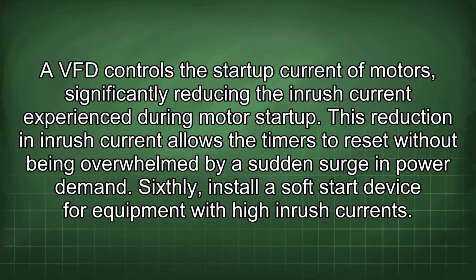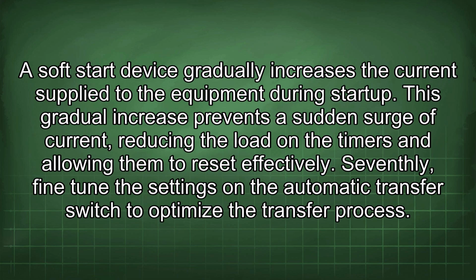A VFD controls the startup current of motors, significantly reducing the inrush current experienced during motor startup. This reduction in inrush current allows the timers to reset without being overwhelmed by a sudden surge in power demand. Sixthly, install a soft start device for equipment with high inrush currents. A soft start device gradually increases the current supplied to the equipment during startup.